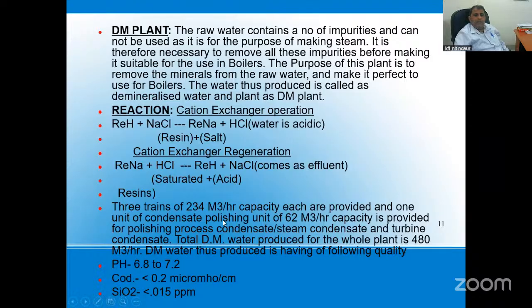As per the plant requirement, how much water is required and how much steam you are generating, depending on the power requirement, the capacity of the DM plant is decided. Our requirement is large, hence 3 trains of 234 meter cube per hour capacity are provided.